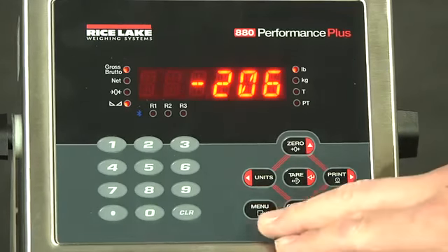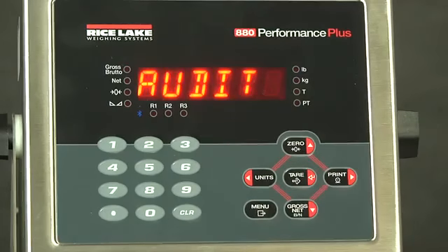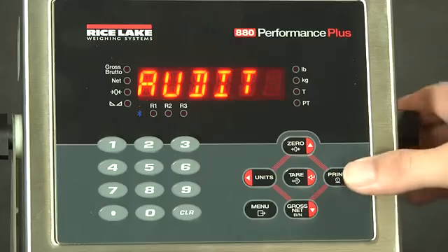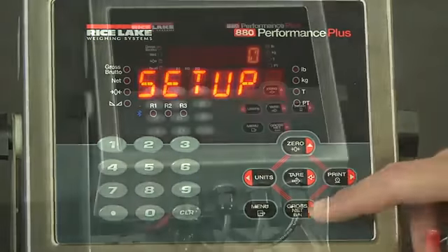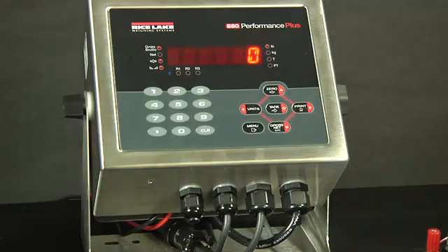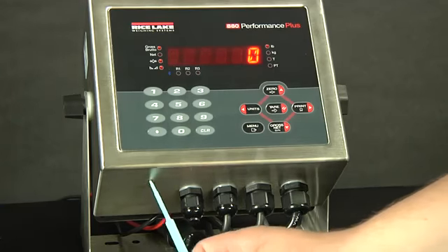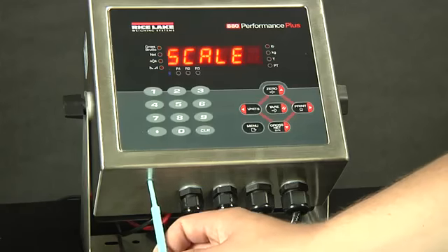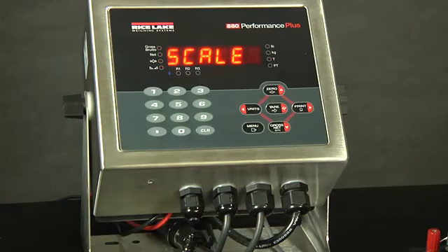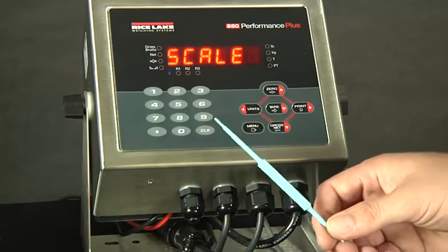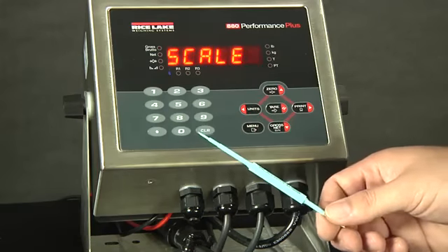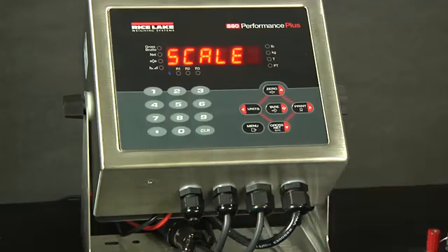So first we're going to access the menu. Now, as long as this is not locked with a configuration password, you will be able to go over to the right to setup. If the setup menu is locked out, you will have to access the physical configuration switch. The switch is available in the lower left-hand corner on the bottom of the unit. As you can see right here, if we push the button, we will access configuration. Notice I am using a plastic tool. Please make sure to never stick metal inside the indicator, as you could chip a board and cause issues.